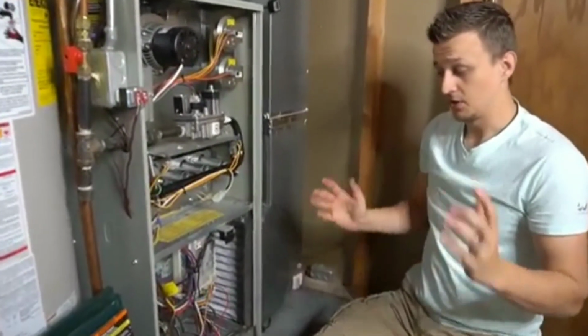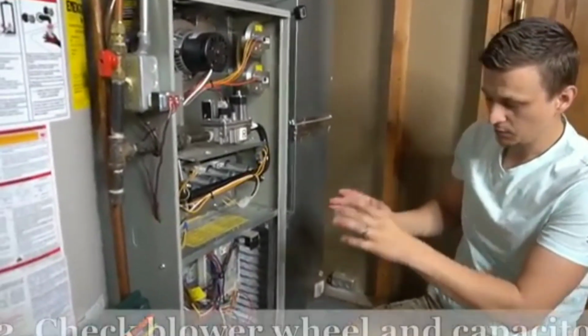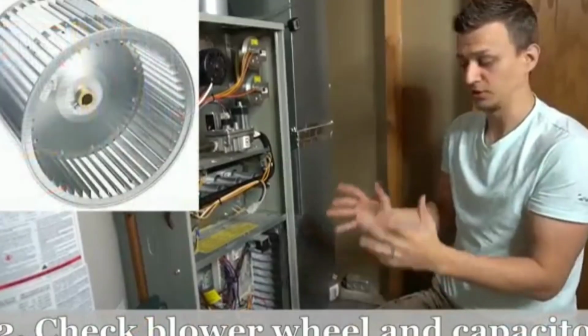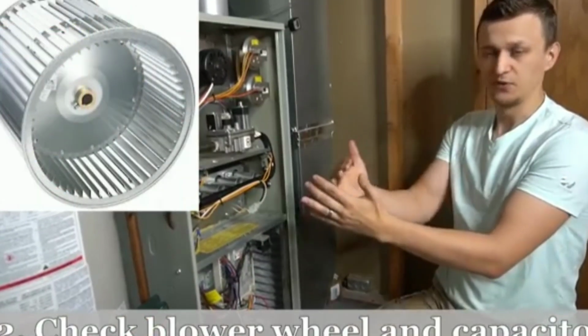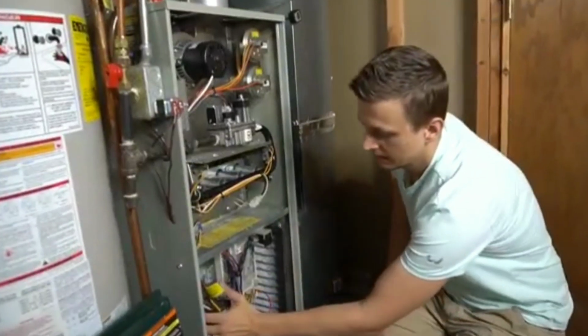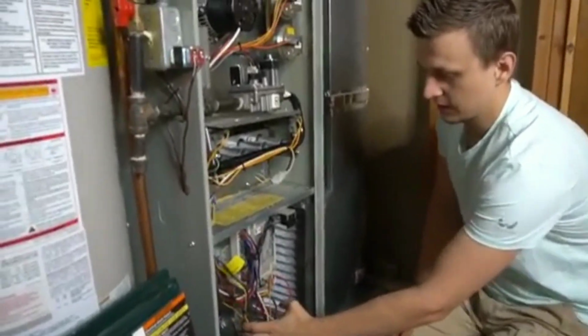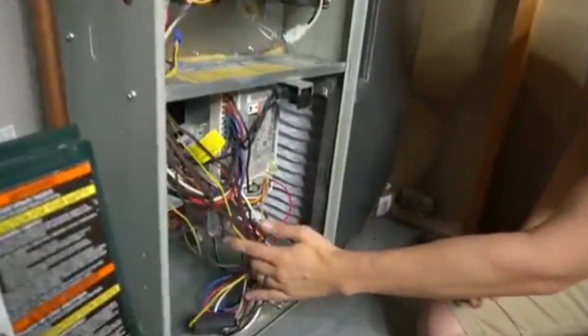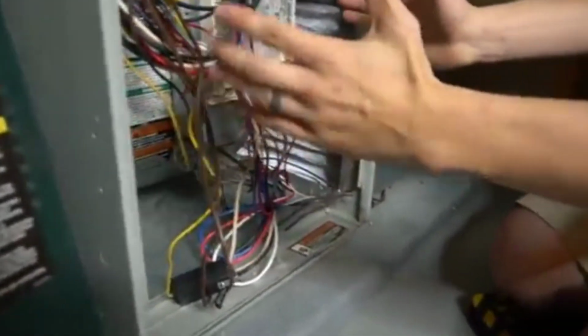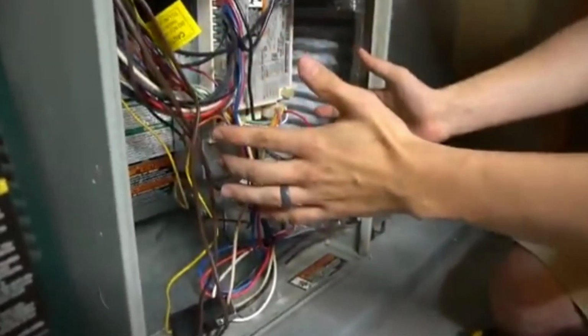And maintenance tip number 12 is the blower motor, or more specifically the blower wheel. The fins on that blower wheel, with time, eventually get plugged up with dust and other debris. So here's an easy way to check if your blower wheel is dirty or not. So here's your blower wheel. You've got this big metal housing.